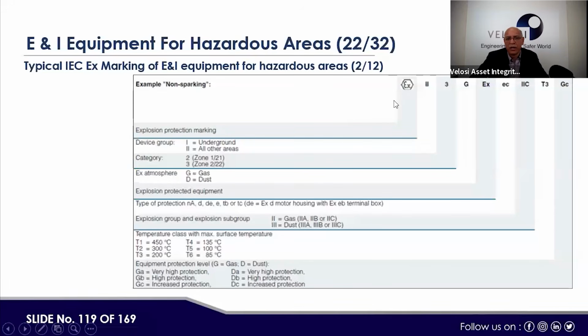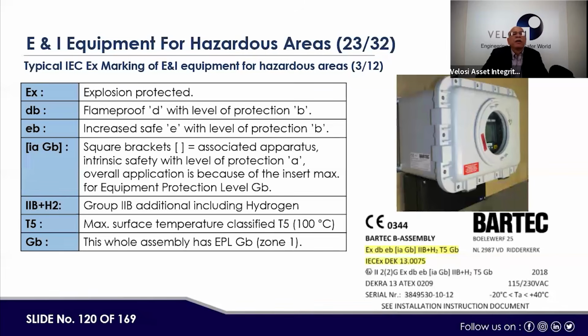When you start looking at the specification of the equipment and practice, you will start understanding. Now the typical IEC marking on an instrumentation equipment for a hazardous area. Here is one of the equipment installations, right? Here the assembly of one of the transmitters is marked Ex db eb [ia Gb] IIB plus H2 T5 Gb. These are all explained here. Now, what is Ex? Explosion protected. Db is flameproof, d with level of protection b. Eb is increased safety, e with level of protection b.